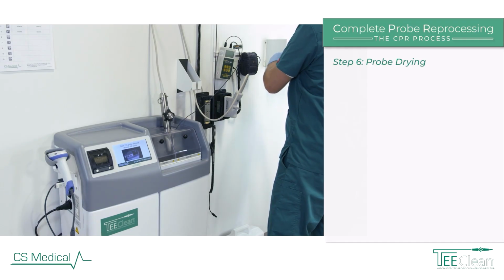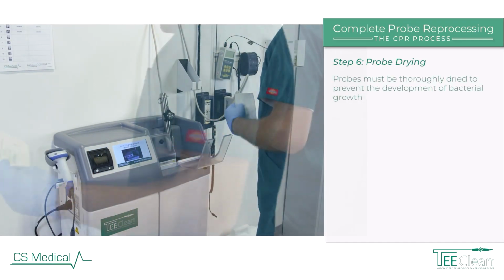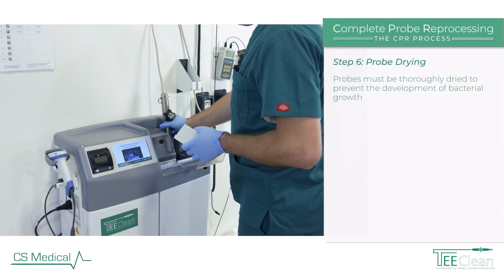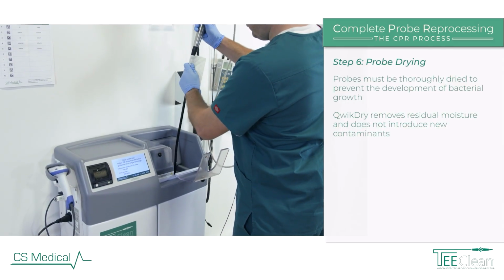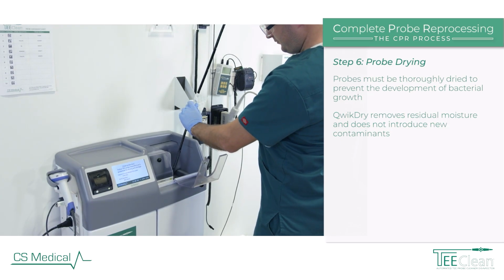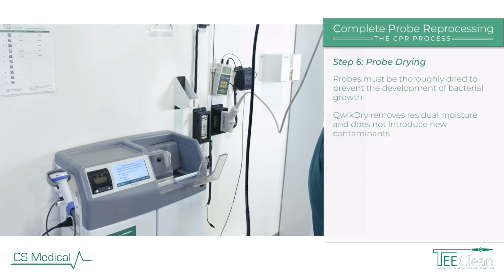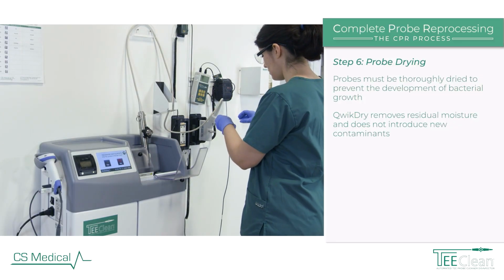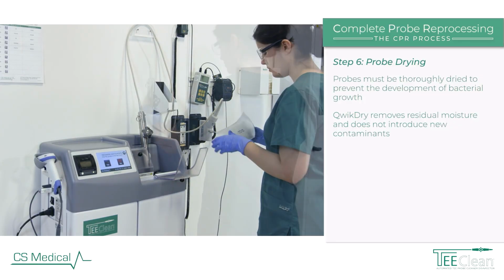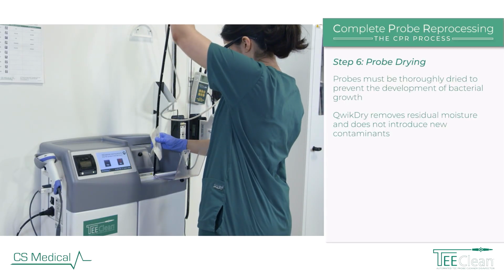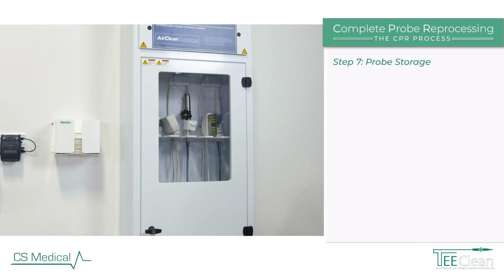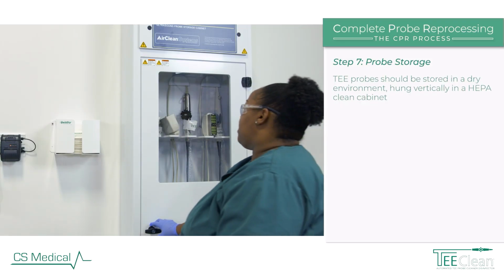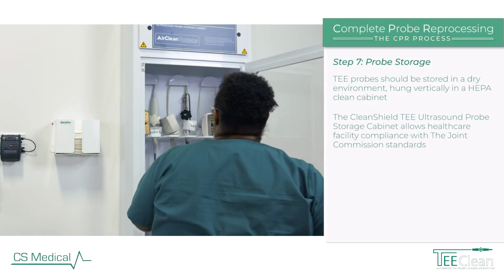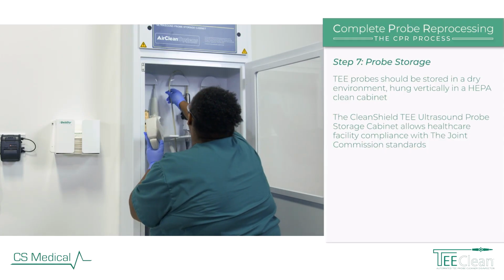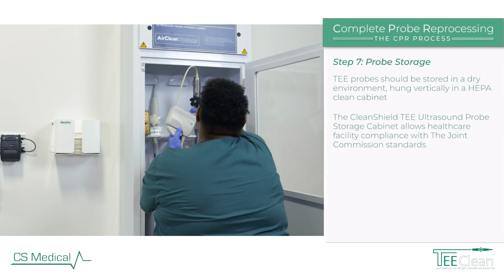Step 6. Probe drying. Upon removal from TEEClean, probes must be thoroughly dried to prevent development of bacterial growth. QwikDry drying cloths are contaminant-free, single-use, gamma-irradiated fabric that slides freely down the insertion shaft of the TEE probe. Packaged in an easy-open pouch, QwikDry removes residual moisture and does not introduce new contaminants to the high-level disinfected TEE probe. Step 7. Probe storage. TEE probes should be stored in a dry environment, hung vertically in a HEPA-clean cabinet. The CleanShield TEE ultrasound probe storage cabinet allows healthcare facility compliance with the Joint Commission standards.